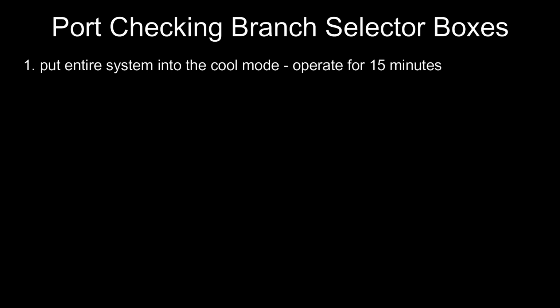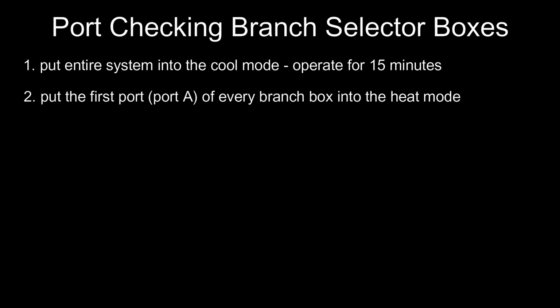To give you the brief version, I will put the entire building into cooling and let it operate for about 10 to 15 minutes. Then I will put the first port of every branch box into the heat mode. Because we are checking for cross-wiring within a particular branch box, we can check for cross-wiring on every single box simultaneously because we are telling each unit wired to each box's port A, for example, to switch to heat. As long as you only change one unit on each box at a time, you're going to be fine following this process.